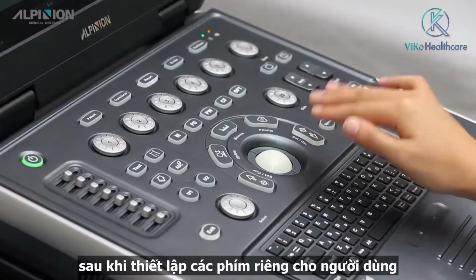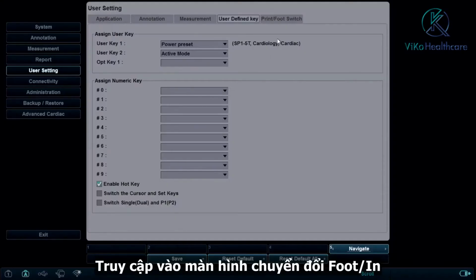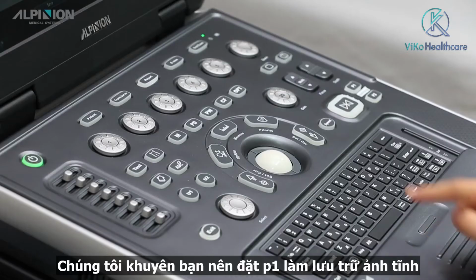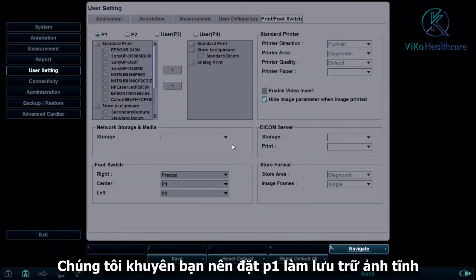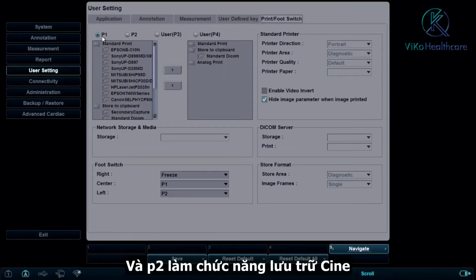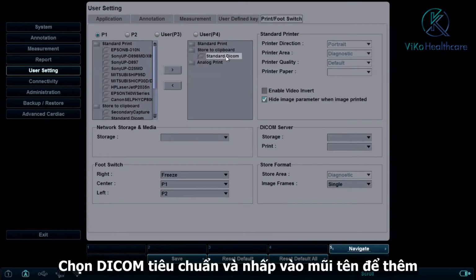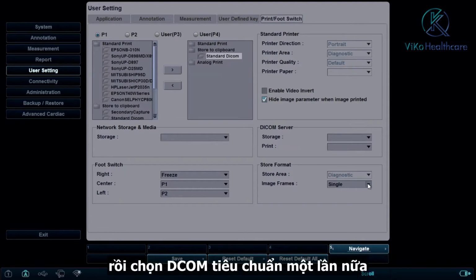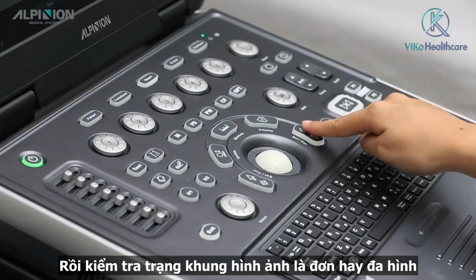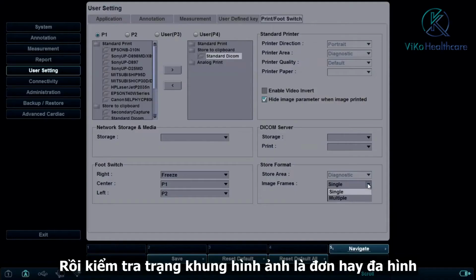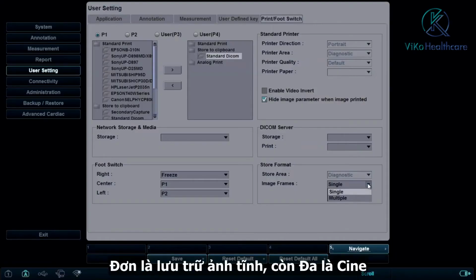After setting UD key, enter the Print Foot switch screen. We recommend you to set P1 as a still image storing and P2 Cine Loop storing function. Select Standard DICOM and click arrow to add on. Then select Standard DICOM again and check the image frame status are single or multiple. Single is still image saving and multiple is Cine.